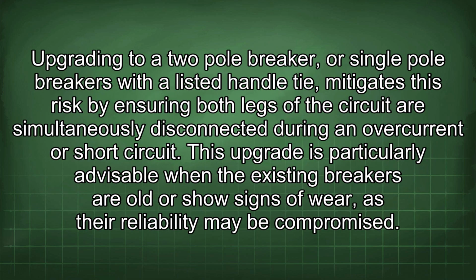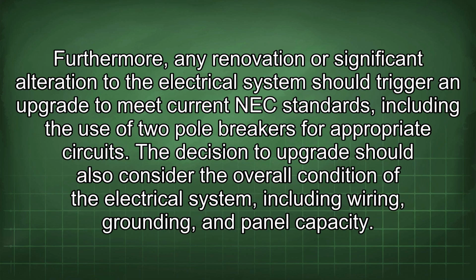Upgrading to a two-pole breaker or single-pole breakers with a listed handle tie mitigates this risk by ensuring both legs of the circuit are simultaneously disconnected during an overcurrent or short circuit. This upgrade is particularly advisable when the existing breakers are old or show signs of wear, as their reliability may be compromised. Furthermore, any renovation or significant alteration to the electrical system should trigger an upgrade to meet current NEC standards, including the use of two-pole breakers for appropriate circuits.